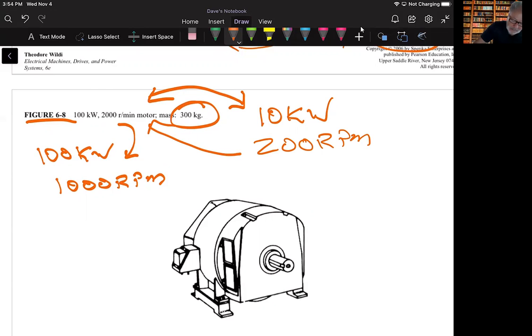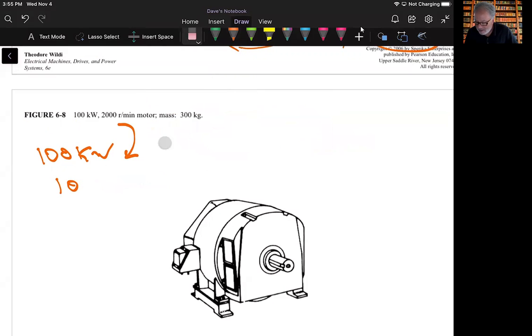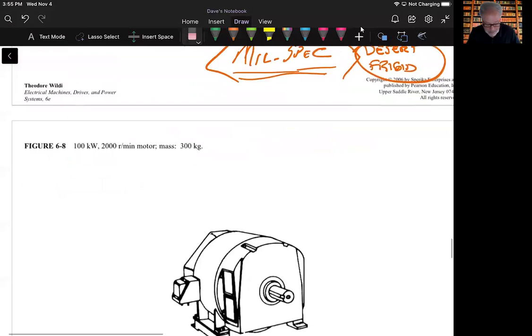Low-speed motors are much more costly than high-speed motors of equal power. The reason for that is the size increase: the copper increase, or the amount of flux or pole size, has to increase. For low-speed drives, it's often cheaper to use the smaller high-speed motor with a gearbox than to use a large low-speed motor directly coupled to its load. Okay, so the advantage goes to the higher speed to get a certain output that we desire, and this goes through the multiple reasons why.